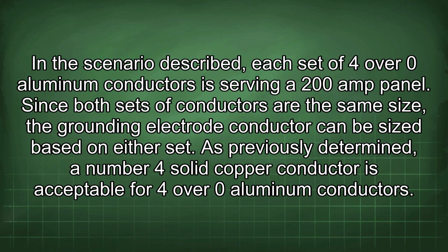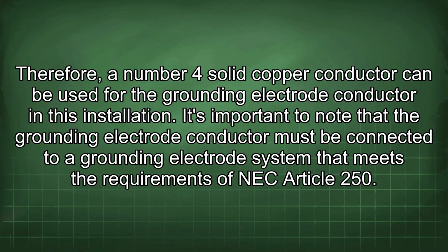In the scenario described, each set of 4/0 aluminum conductors is serving a 200 amp panel. Since both sets of conductors are the same size, the grounding electrode conductor can be sized based on either set. As previously determined, a number 4 solid copper conductor is acceptable for 4/0 aluminum conductors. Therefore, a number 4 solid copper conductor can be used for the grounding electrode conductor in this installation.